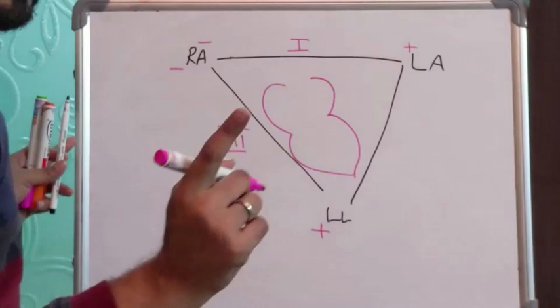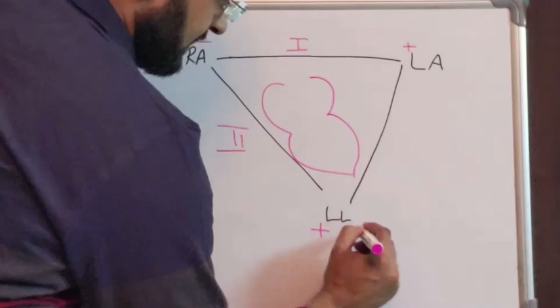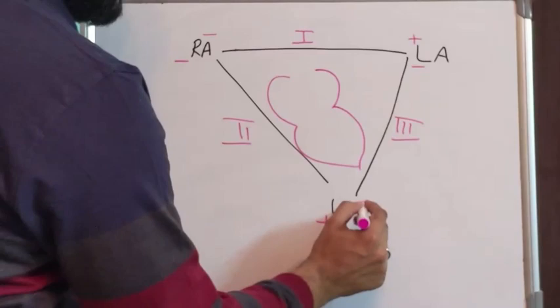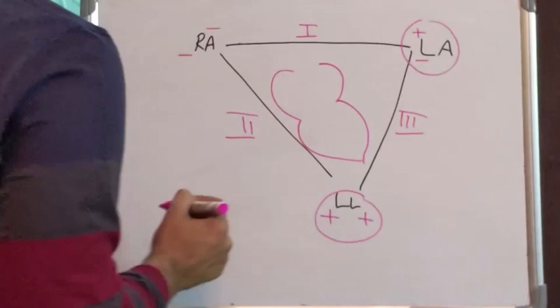And this is where I had made a mistake in the last video. The lead with the positive electrode at the left leg and the negative electrode at the left arm is lead 3. So the left leg has got positive electrodes of 2 and 3. The left arm has got one positive and one negative whereas the right arm has got both negative electrodes.